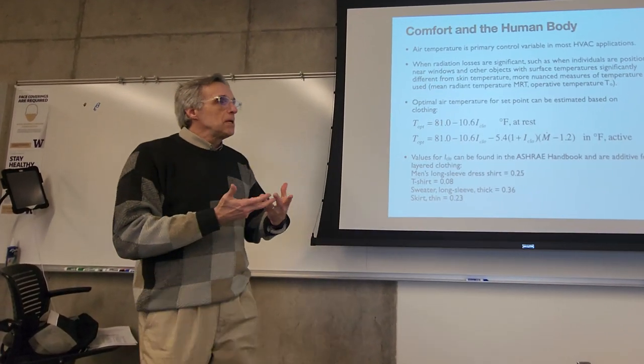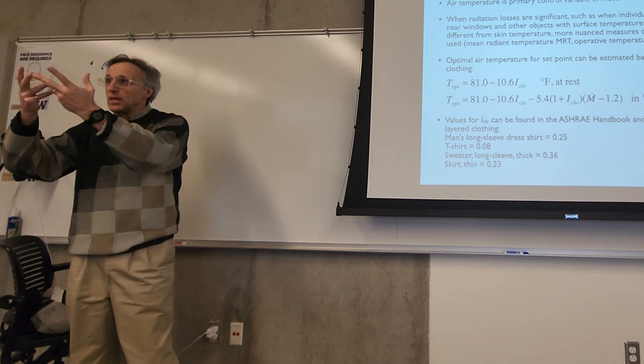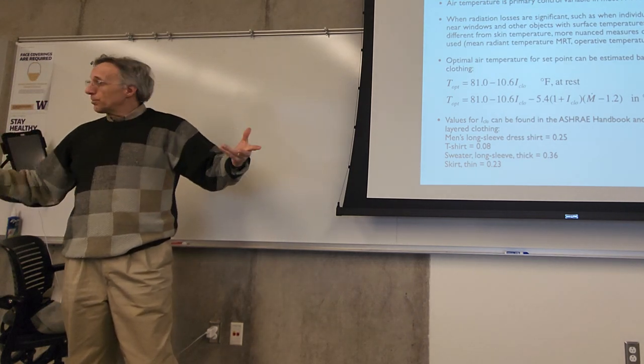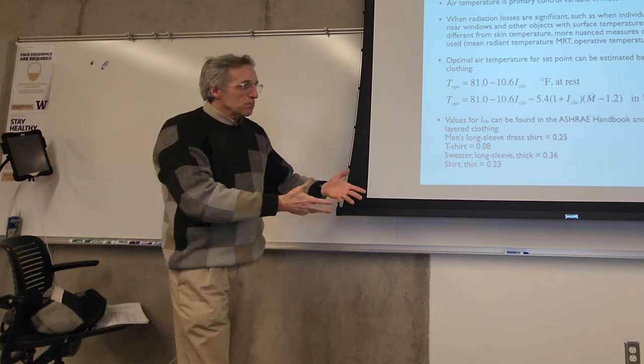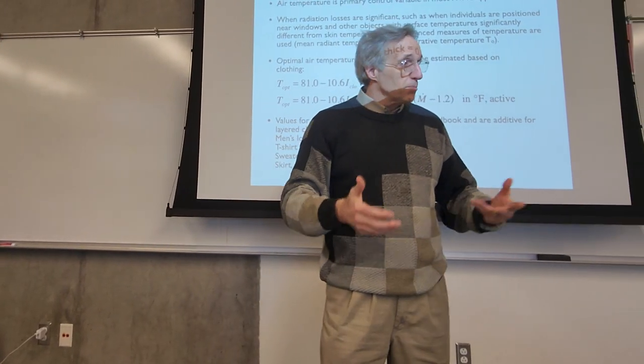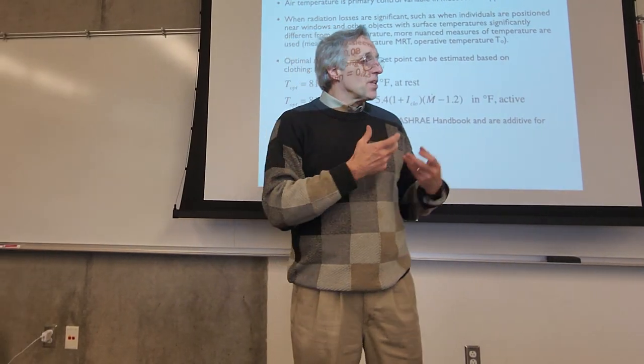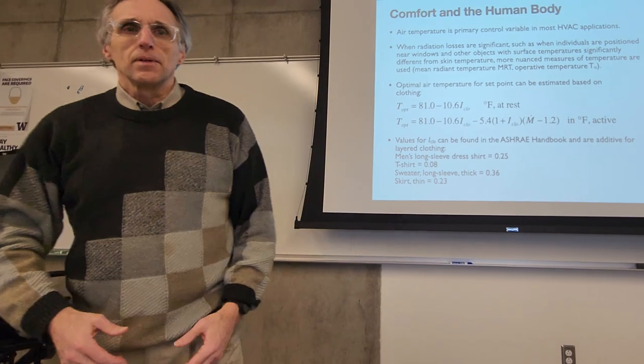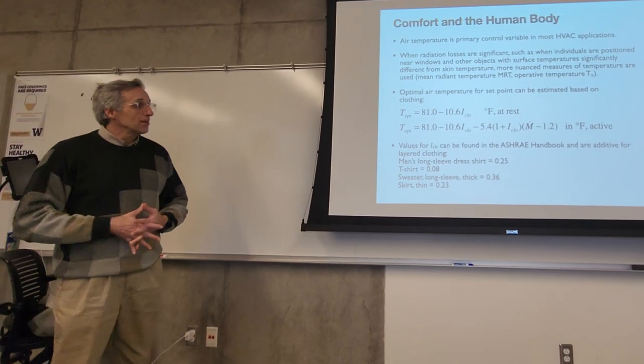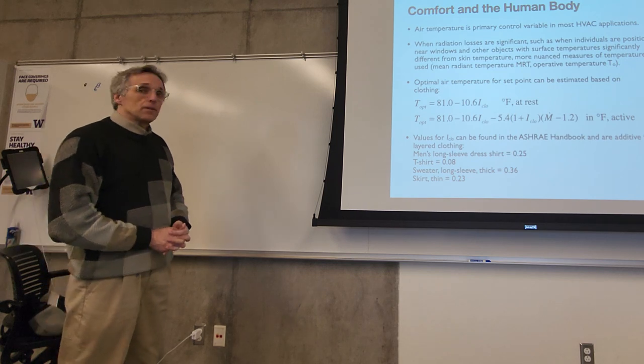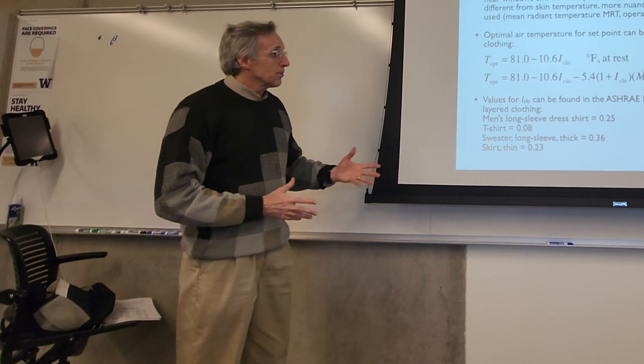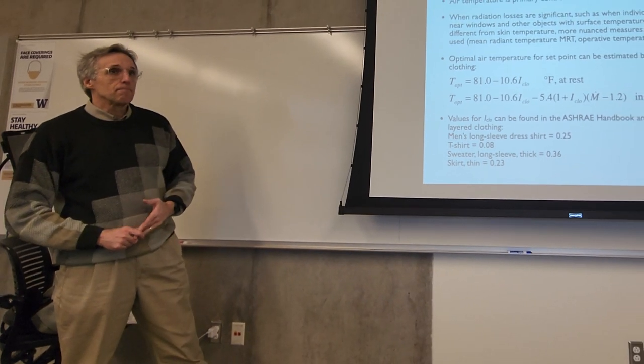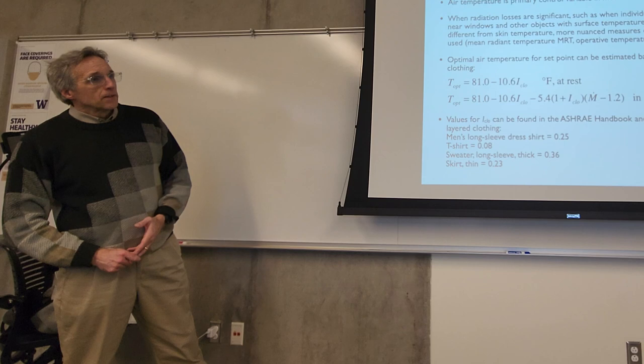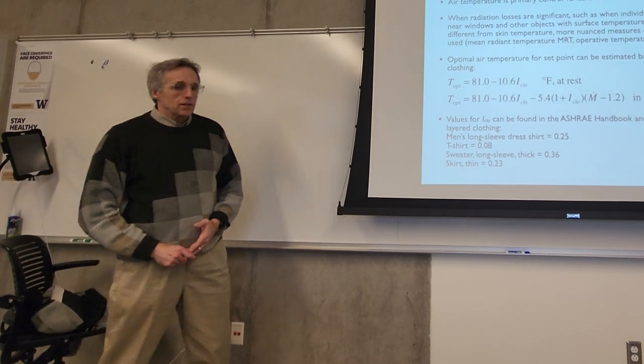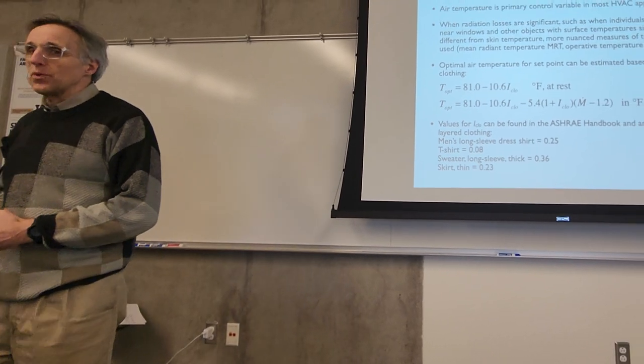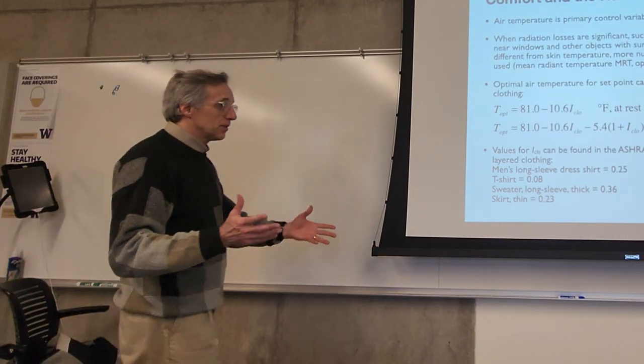And that is thought to be more accurate because it includes not just the temperature of the air, but also the temperature resulting from radiation. As radiation comes in, it will cause some surfaces to be hotter than the surrounding air, and maybe some surfaces will be colder than the surrounding air. So that gives you a more exact measure of the thermal condition in the room. But it is hard to calculate. There's a complicated formula that I don't even bother with. I think the HVAC software will actually calculate that for us. Plug in the climate and a bunch of other data.